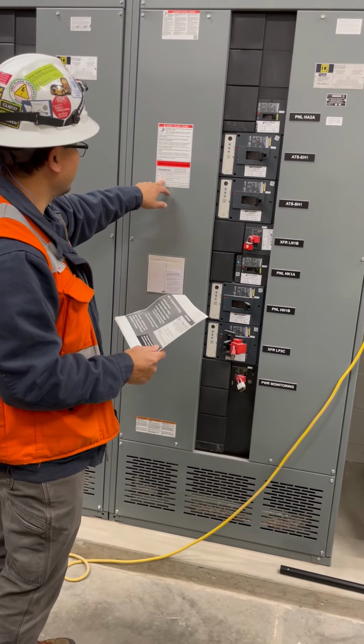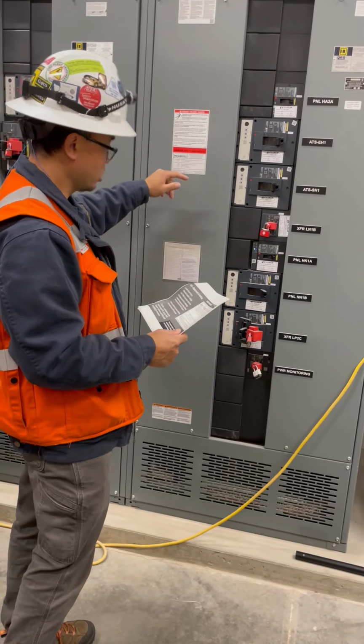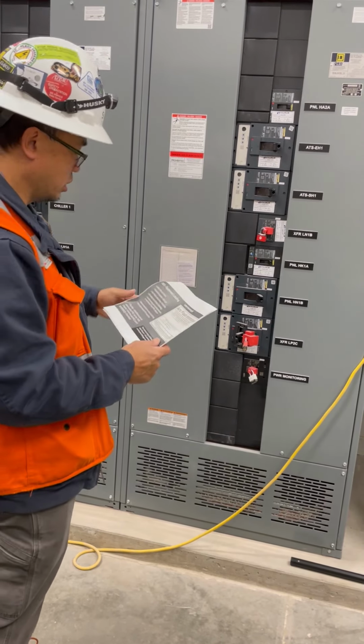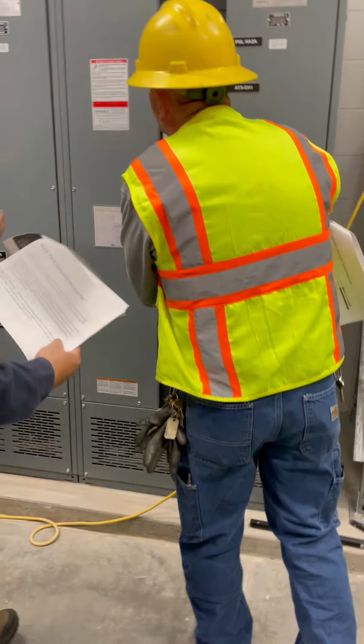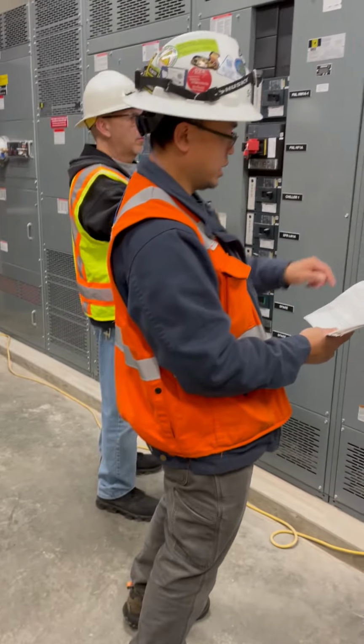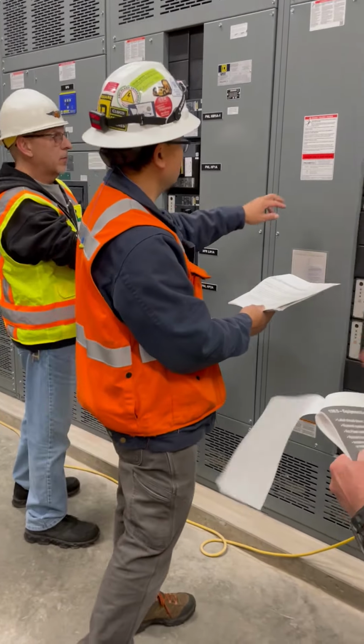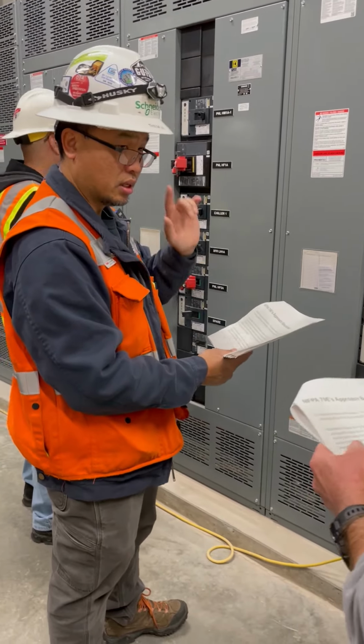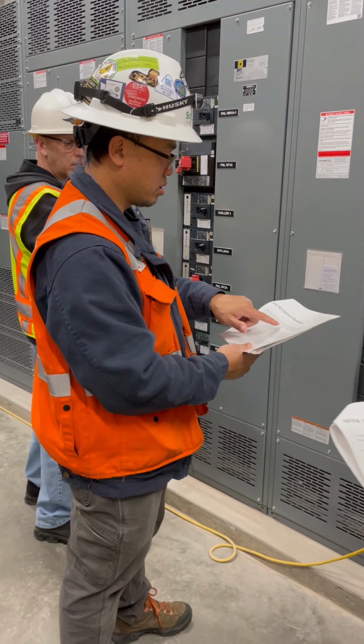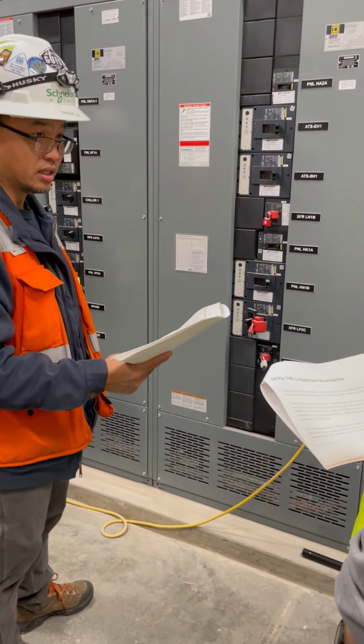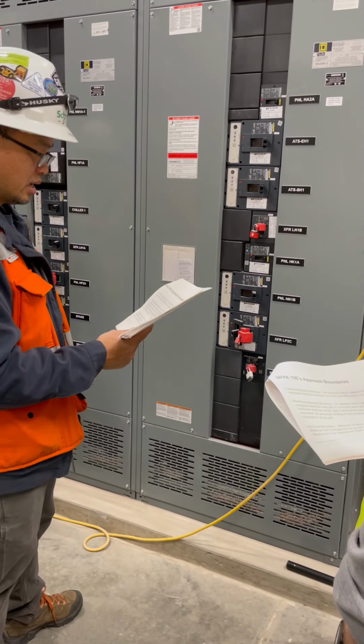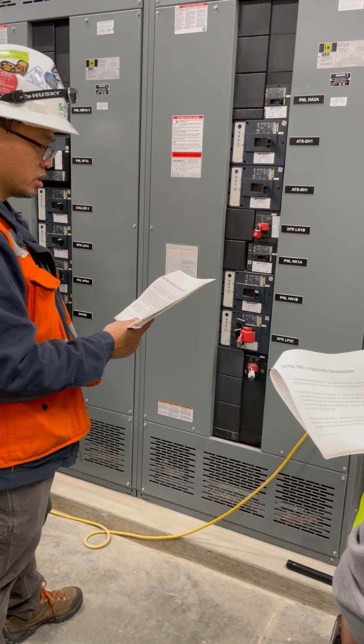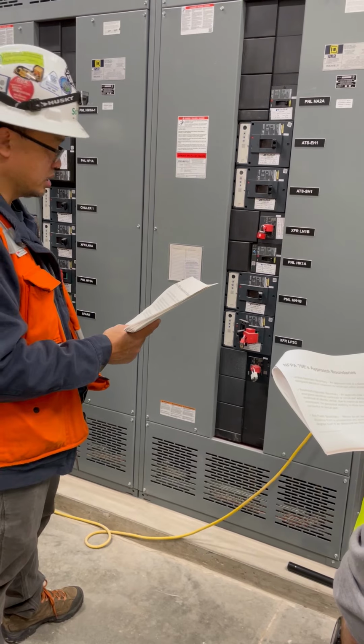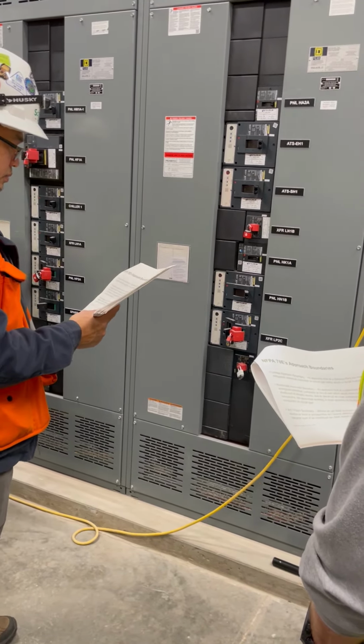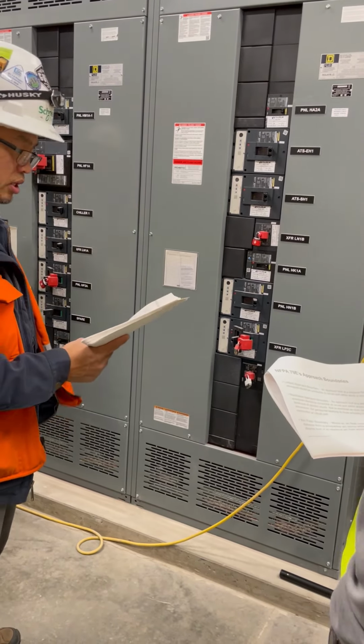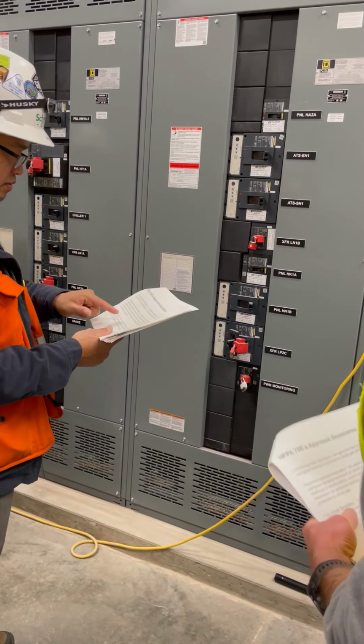The other portion of the label is 480, that's the nominal voltage. Then the limited and restricted approach, those are fixed, based on the voltage level. This will give you the definition of what a limited approach, restricted approach and arc flash boundary are. A limited approach is an approach limit at a distance from an exposed, the critical word here, exposed, energized electrical conductor or circuit part within which a shock hazard exists. The restricted approach is an approach limit at a distance from an exposed energized electrical conductor or circuit part within which there is an increased likelihood of electric shock. It's almost like you're next to it, so any inadvertent movement, or if there's an arc, you can be exposed to shock. And of course, the arc flash boundary is where an arc flash exists.